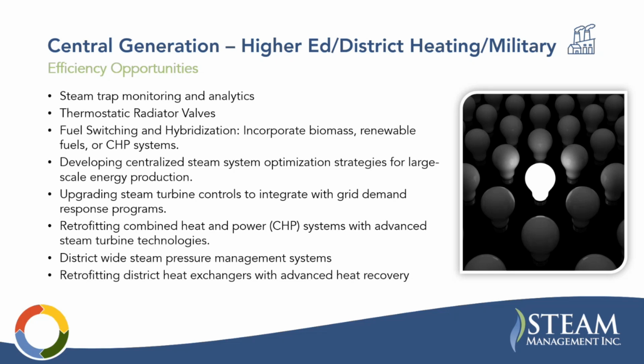You have fuel switching and hybridization, so you can incorporate other fuels like biomass or renewable fuels, or combined heat and power systems. You can also develop centralized steam system optimization strategies for large scale energy production. If they do have combined heat and power, you can upgrade steam turbines to control grid demand response programs. There's district-wide steam pressure management systems, and then retrofitting district heat exchangers with advanced heat recovery - basically replacing equipment with higher efficiency equipment.